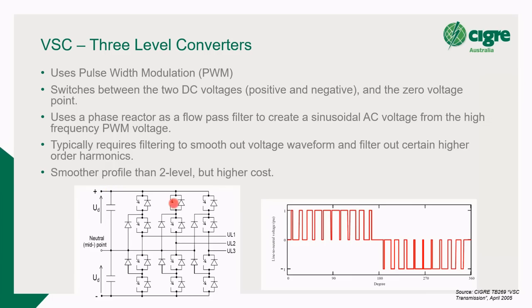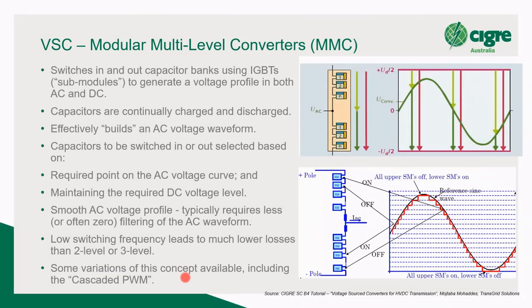If you look at this diagram here, there are many more IGBTs in here than there are in the two level. And that means higher capital cost and possibly higher operational costs and possibly losses. But eventually over time, it was determined that there was a better way to actually reduce switching frequency, and that's the multi-level. In my view, if you're building a large VSC, there's a very, very good chance it's going to be a multi-level. The two level is good for smaller projects, maybe offshore platforms or small islands that you're connecting to, but the multi-level really is quite a significant breakthrough in technology.